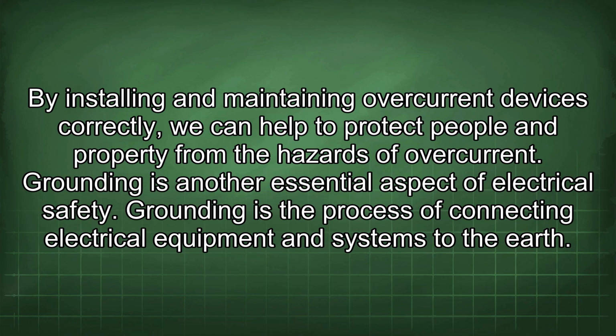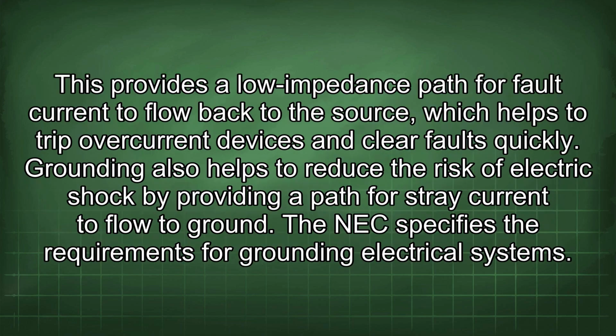Grounding is another essential aspect of electrical safety. Grounding is the process of connecting electrical equipment and systems to the earth. This provides a low impedance path for fault current to flow back to the source, which helps to trip overcurrent devices and clear faults quickly. Grounding also helps to reduce the risk of electric shock by providing a path for stray current to flow to ground. The NEC specifies the requirements for grounding electrical systems.